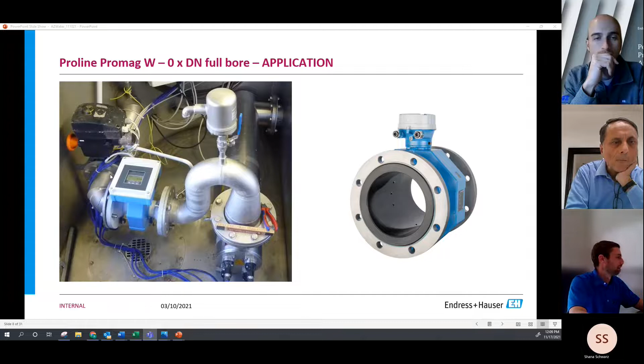And the newer components can be seen on the side here. We have 1, 2, and 3 measuring electrodes on each side. So a total of 6 measuring electrodes, which allows for more averaging of the flow profile. So if you think about getting turbulent flow, non-homogeneous flow, essentially what the meter is doing is it's taking more information and it's averaging the different flow profiles. On the left-hand side, it kind of gives you an idea, even though this isn't fully bolted in, the concept is that pipe bends, any sort of pipe bends in any axis, X, Y, Z axis, the meter can handle much easier. And again, no pressure losses.